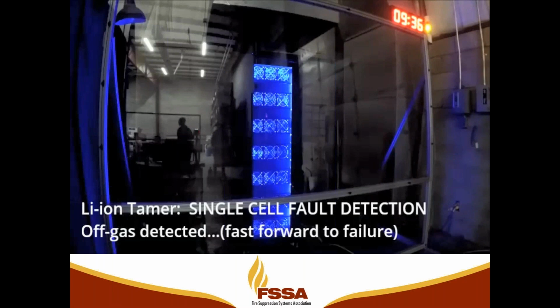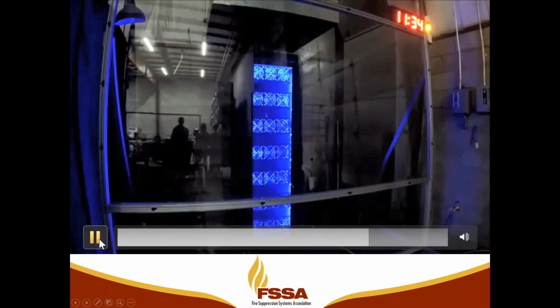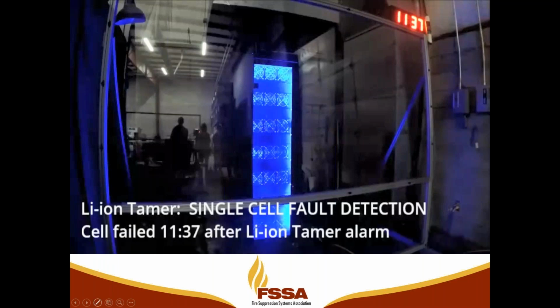So now the off-gas monitor has detected an off-gas event, and the timer is started, and we're now in the golden time for early warning detection. So at this time, hopefully we're working in conjunction with the battery management system to eliminate the overcharging. Now you can see full thermal runaway was achieved at 11 minutes and 37 seconds after off-gas was detected. So that golden time here was 11 minutes and 37 seconds.